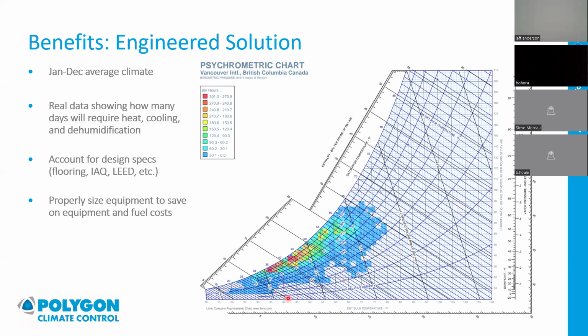So this is just a psychrometric chart. It looks super complex, but it's not that complex. You've got temperature on the bottom, cold is on the left, hot is on the right. These curved lines are your relative humidity lines. So as you get hotter, relative humidity drops because hot air can hold more moisture. Air expands, its ability to hold moisture grows. And then over here, you've got absolute moisture levels, which is not something people commonly look at, but that's super important for vapor pressure and for engineering this stuff.